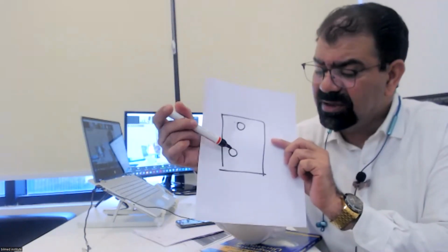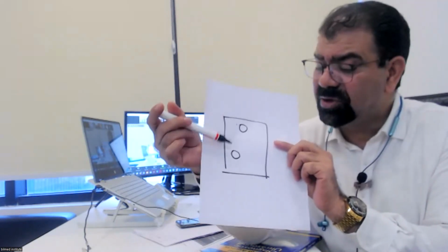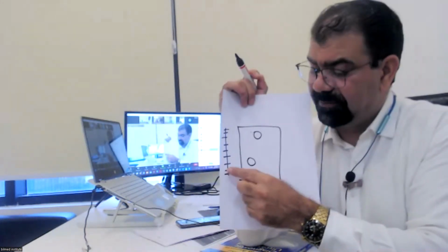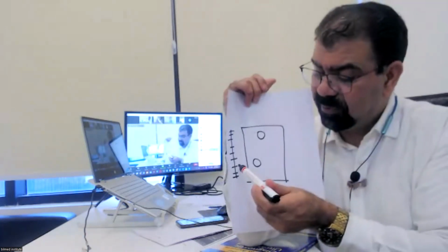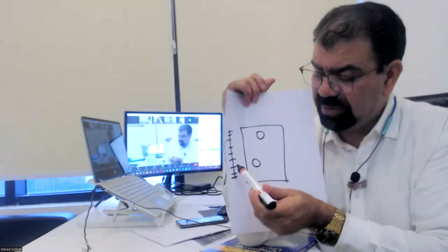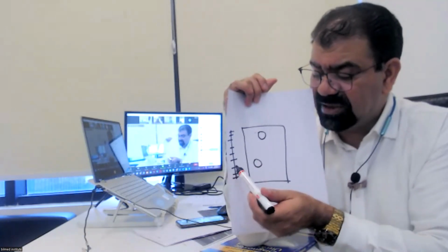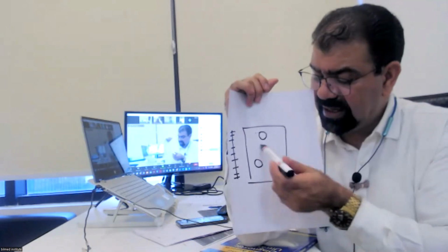Now, this is in the bottommost part. This is not on the top. Here comes the role of TGC. Now, TGC is not a knob over there, but some sliders like this. I will see which slider will work for this area, and this has to be, for example, maybe a third or a fourth over here. So by sliding this TGC, the gain of this area will decrease or increase.